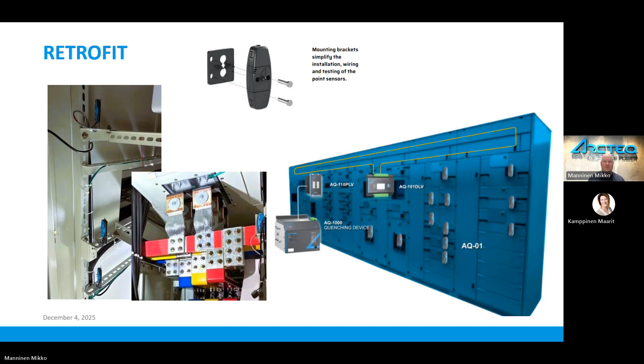It is a retrofit installation, and then the bracket here is built for easier retrofitting and easier testing and installation of the sensors. So you can drill this bracket inside the panel board or switchgear, and then just push that sensor on top of that bracket. And if you need to test it, or if you need to turn it another way around, you can just remove it, change it and put it back. Very easy to use.